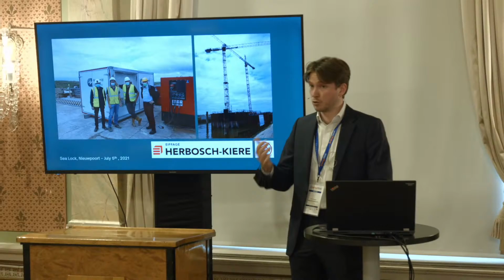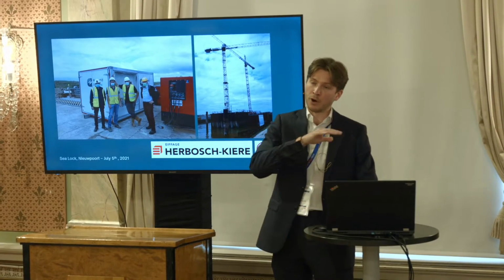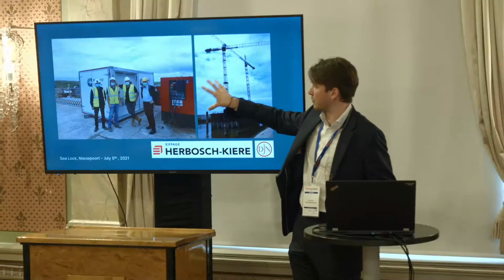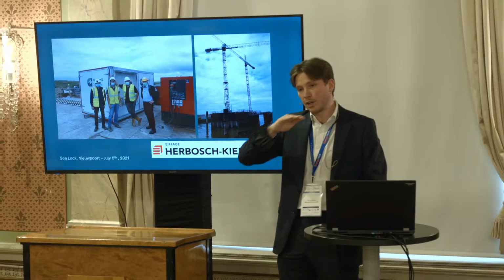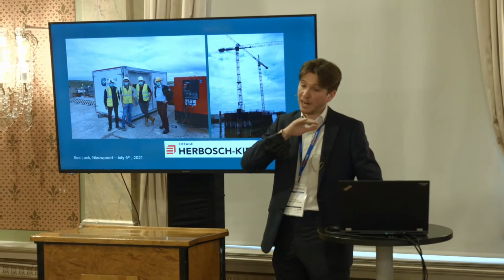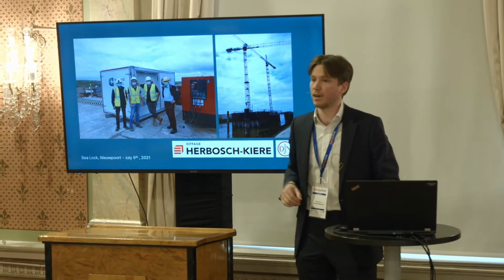Those diesel generators would be running at a very low load with very little efficiency, up to 5%, just for powering those tower cranes. Here we have a diesel generator of 60 kVA, a smaller one, running at a very efficient speed and able to provide 30% efficiency.